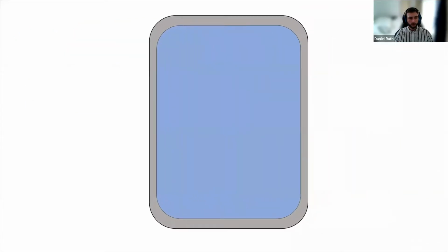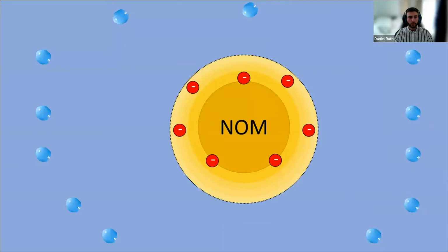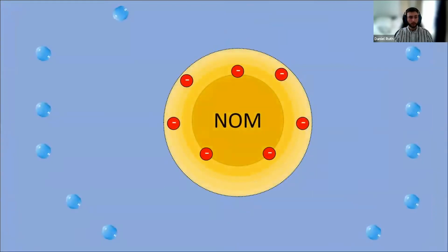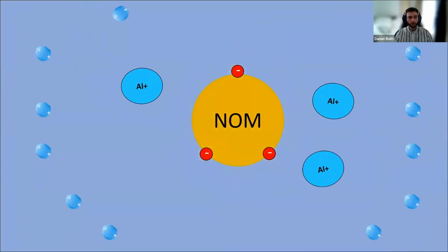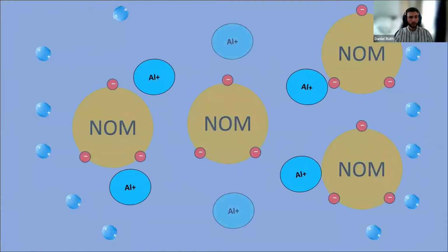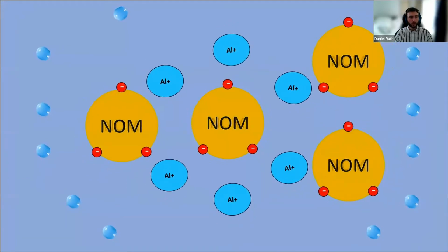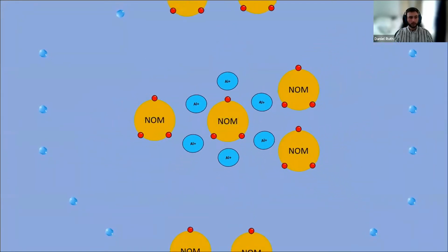Water treatment works abstract water from reservoirs and therefore must remove the organic matter. The process utilized for this is coagulation. Coagulation is needed as a negative charge in the organic matter causes repulsion. This makes it difficult to remove. In order to remove the organic matter, a positive coagulant, which is generally a metal salt, is added to the water. In this example, aluminium sulfate has been added. The positive charge in the coagulant reduces the overall charge of the organic matter, allowing them to flocculate together. The flocculated organic matter is then removed using dissolved air bubbles, which push them back to the top of the vessel where they can be more easily removed.